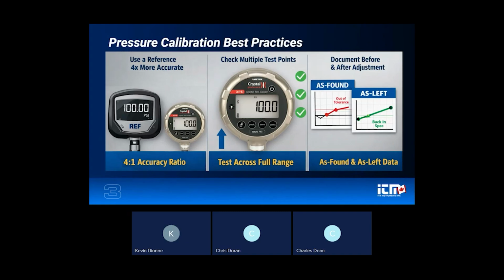And this brings us to one of the most important practices that, once again, I often tell my customers if they're looking for new methods: performing as found and as left readings. As found data shows you exactly how the instrument was performing when it came out of service. It tells you whether the gauge was still within tolerance, how much it had drifted if it had, and whether there may be any developing issues with the instrument or the process itself. As left data confirms that the instrument was properly adjusted and returned to specification before being placed back into service. So together, as found and as left results give a clear and historical record of performance over time. This historical data is extremely valuable. It allows you to identify trends, justify calibration intervals, and catch potential problems early.